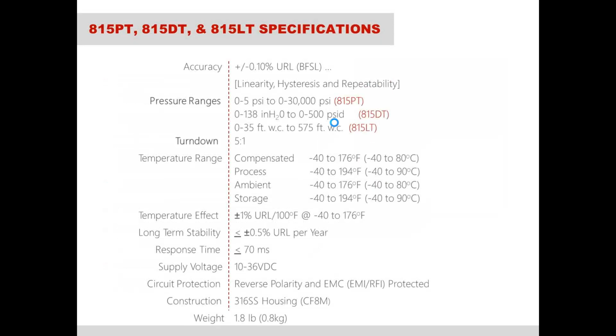Here are some of the specs for the 815 PT, DT, and LT. We've already gone over the pressure ranges, but the accuracy on the 815 series is 0.1%, so a very good accuracy. Almost all the time this accuracy will be good enough for what they'll need. There are sometimes when we're competing against a Rosemount or someone like that that has a 0.075% accuracy or a 0.05% accuracy, that the customer requires that, and maybe there are some things that we can do to get there, but if they're requiring that much accuracy, then they probably need to go with that Rosemount or someone else. The response time is less than 70 milliseconds.